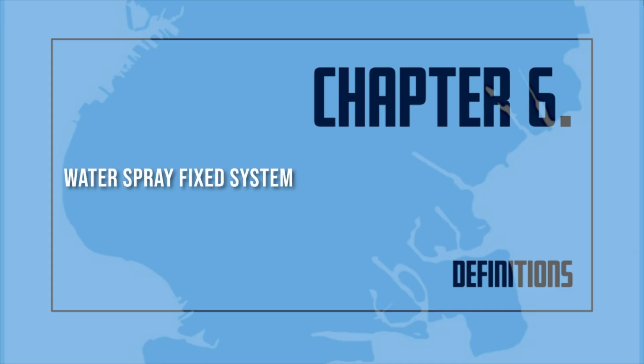Water spray fixed system. A special fixed pipe system connected to a reliable fire protection water supply and equipped with water spray nozzles for specific water discharge and distribution over the surface or area to be protected. The piping system is connected to the water supply through an automatically or manually actuated valve that initiates the flow of water. An automatic valve is actuated by operation of automatic detection or manual release equipment installed in the same areas as the water spray nozzles. In special cases, the automatic detection system may also be located in another area. Water tank. A tank supplying water for water-based fire protection systems.